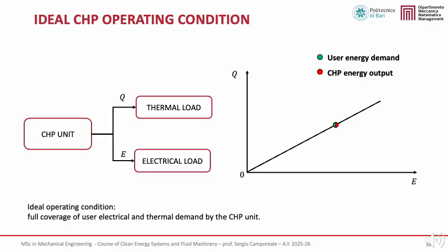We begin with the ideal CHP operating condition. In this case, the operating point of the CHP unit exactly coincides with the user's energy demand. Both the electrical demand and the thermal demand are fully covered by the CHP unit without the need for interaction with the electricity grid or auxiliary thermal systems. In the QE plane, this condition is represented by the overlap between the user demand point and the CHP operating point along the system characteristic. This represents the reference case corresponding to perfect load matching, maximum heat utilization, and the highest potential primary energy savings.